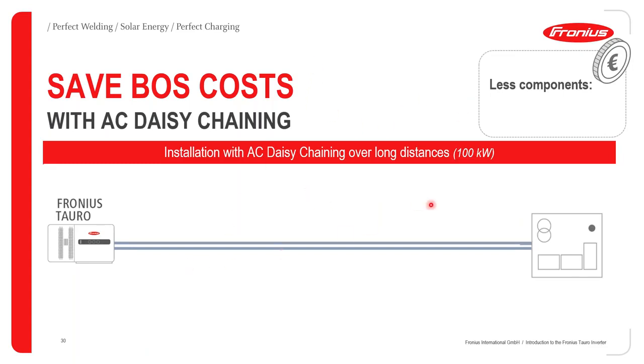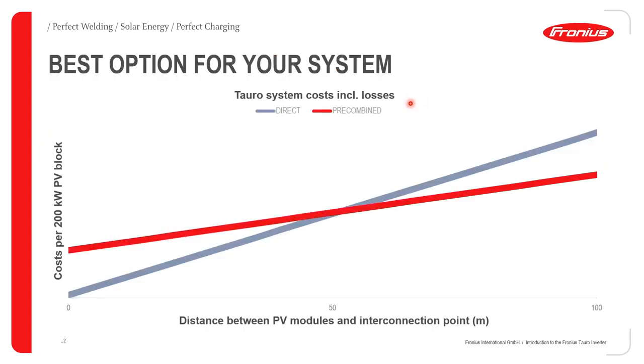So let's now look at how to use the Tauro inverter for longer distances. In this particular case, we are talking about connecting a 100 kilowatt Tauro inverter to a transformer. And in this case, the power losses can be summarized as we can see in this graph: we are considering whether you are going to compare the direct version or the pre-combined version. Starting off from a neutral position here, which we can call 50 meters to the transformer, anytime you are 50 meters and below to the transformer, we can see that the cost of your balance of system components will be much lower when you use a direct version of the Tauro.